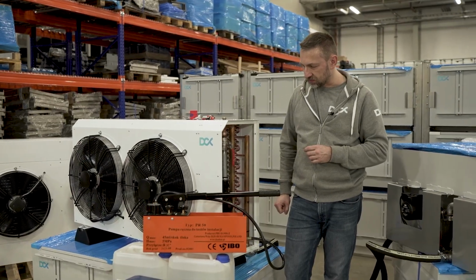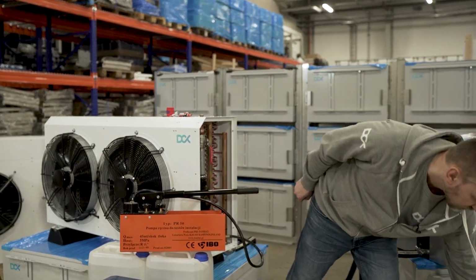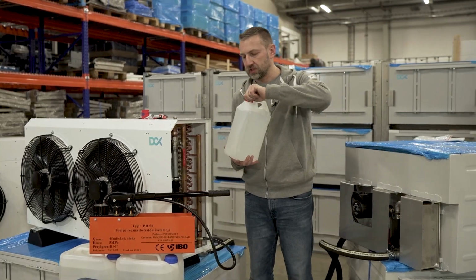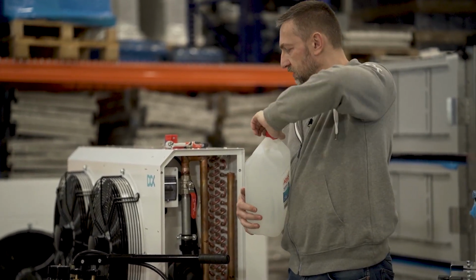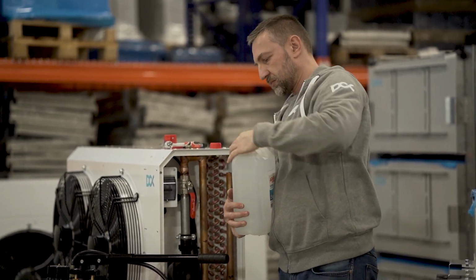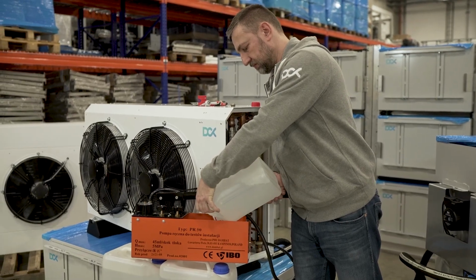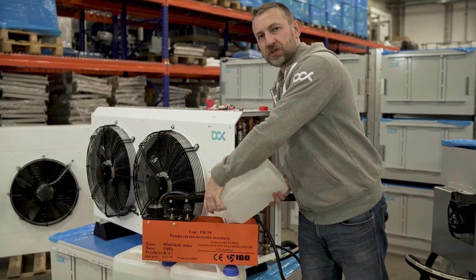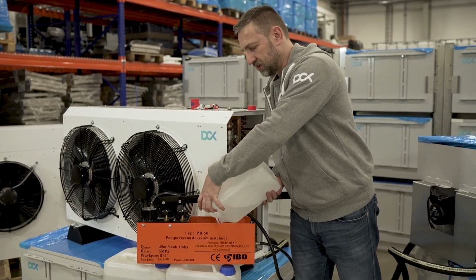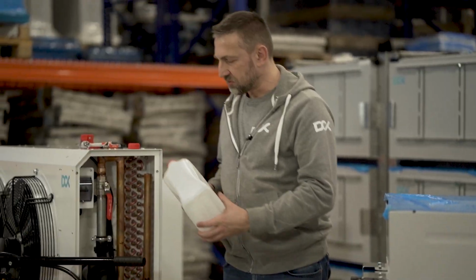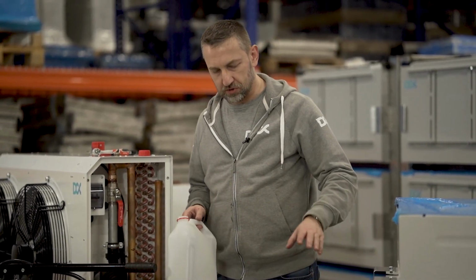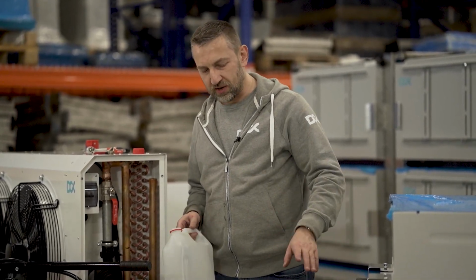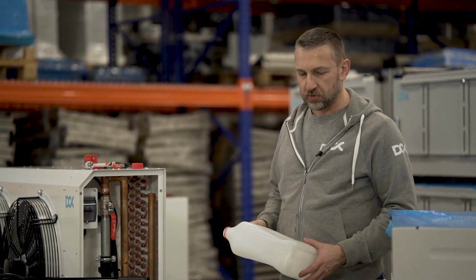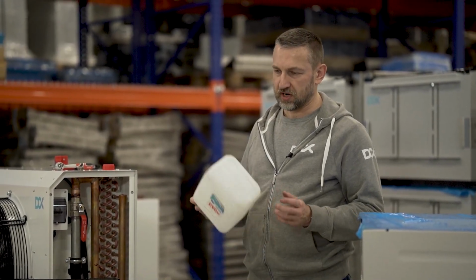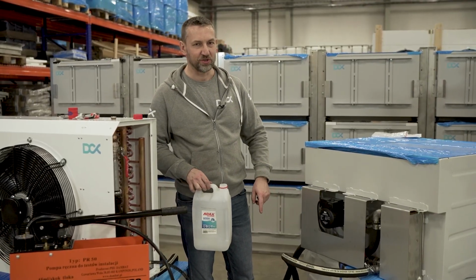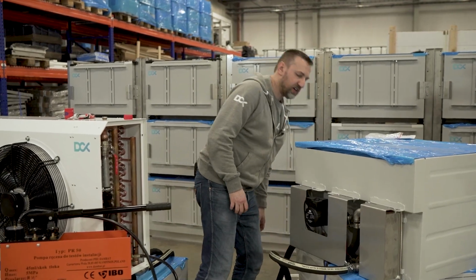When we pressurize this system, we need to add the water into the compartment of that pump. So I'll just show you how to do that pretty quickly. Just put the water inside. In most countries it's pretty cheap to buy, and it's used for ironing and other purposes. For the ICP40, if the tubing is long enough, say you use 10 meters of tubing, so 20 meters altogether, then you may require 15 liters of demineralized water. Here I have 5 liters. But in our case, since we have a very short tube, we may use less than 10. We'll see how much we will require.